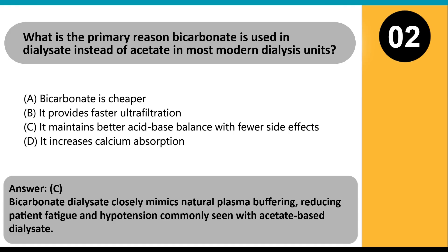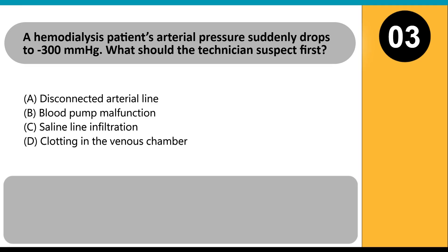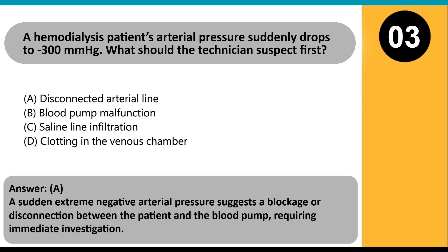Answer C. Bicarbonate dialysate closely mimics natural plasma buffering, reducing patient fatigue and hypotension commonly seen with acetate-based dialysate. A hemodialysis patient's arterial pressure suddenly drops to minus 300 millimeters of mercury. What should the technician suspect first? A. Disconnected arterial line. B. Blood pump malfunction. C. Saline line infiltration. D. Clotting in the venous chamber. Answer A. A sudden extreme negative arterial pressure suggests a blockage or disconnection between the patient and the blood pump, requiring immediate investigation.